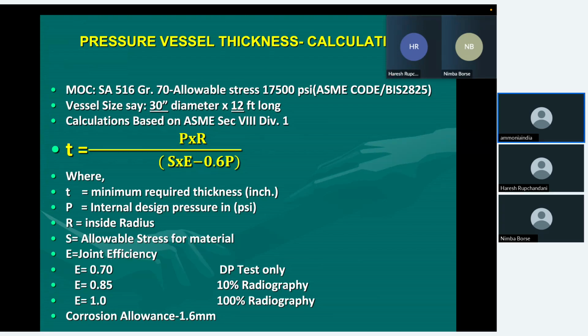Now, how to calculate the thickness? The formula for thickness is pressure times internal radius, divided by the allowable stress of the material times joint efficiency minus 0.6 times the internal pressure.